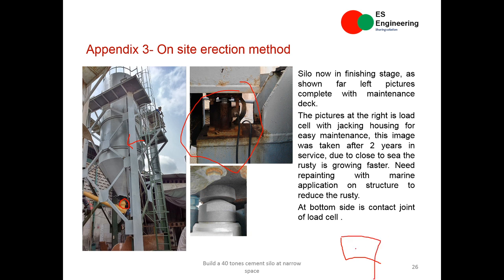We do trimming because in the junction box there is actually a thermistor to adjust it, and then transfer. So the load cell directly reads the weight of the silo and the weight of the screw conveyor here. If that is already good and also calibrated in their laboratory, I only need to press tare, zeroing, and then I put the material inside. So that's already correct. In case you are also facing the same problem and want to apply this, be careful. You have to order the load cell from the same company, order the indicator from the same company, and ask them to do calibration of the load cell together with your load cell indicator. So when the product arrives, you just need to press the tare button. That's all. If you don't do that, it's quite challenging.